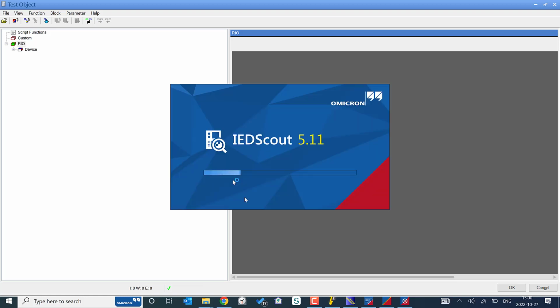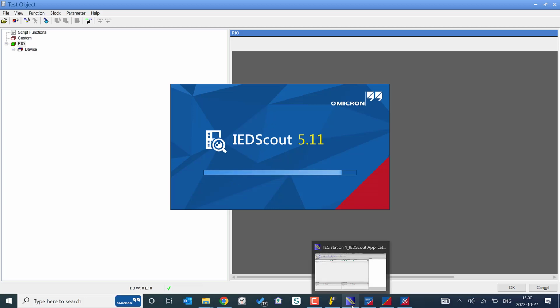There you are able to discover the IED with the IP address information. Also, you can import the SCL file. You can go online to make sure that the configurations are properly loaded and IED Scout is able to connect, and enable the reports and subscribe to the GOOSE messages.